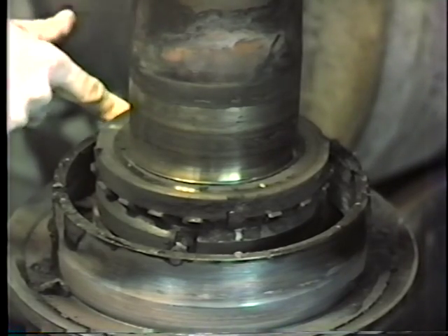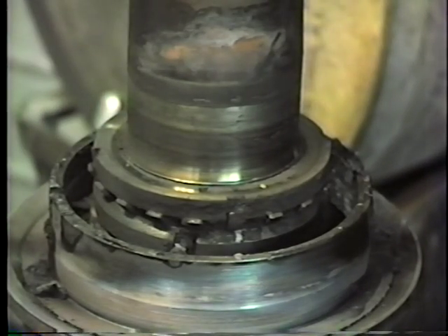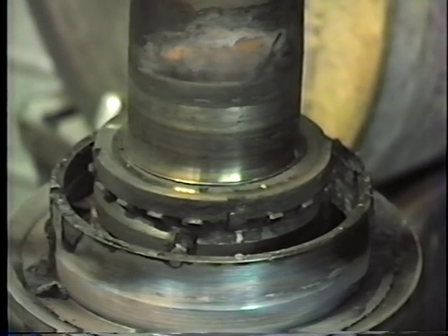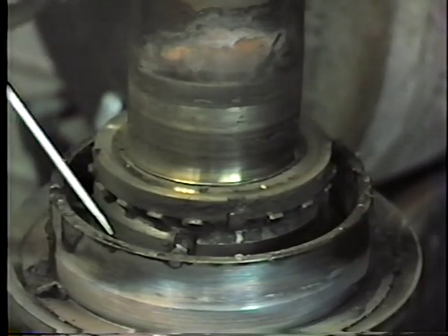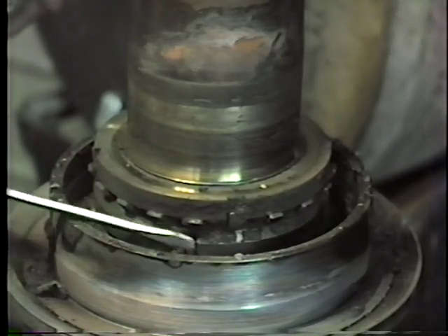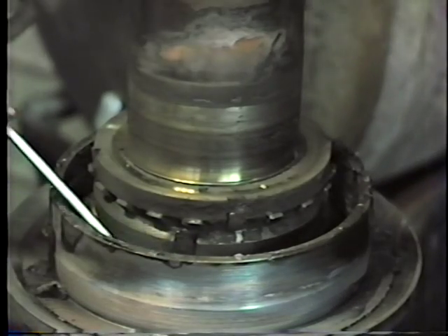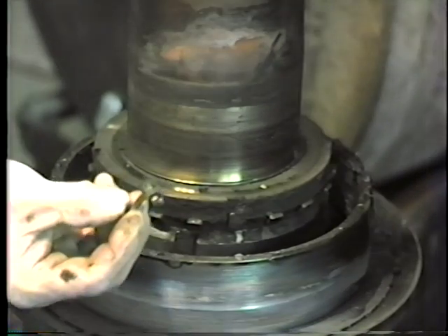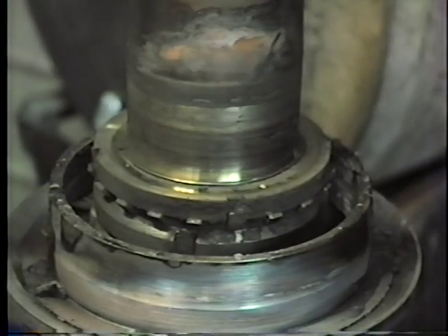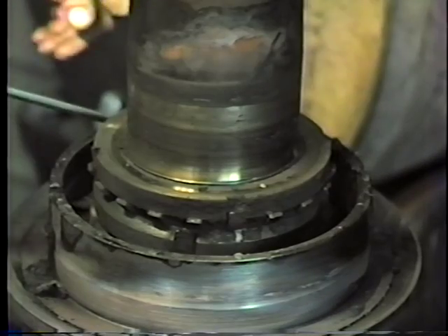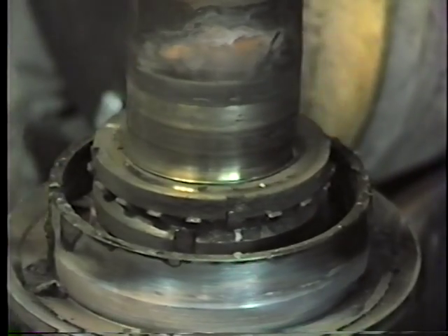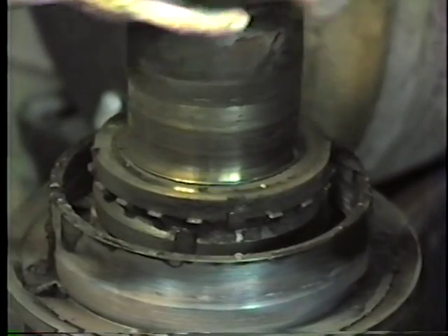You got a screwdriver or something to show me what you're talking about? We have a bearing cage that is just torn all to pieces. That's the bearing outer cage. Push that around so I can see it, please. Pull it right down there where it was.